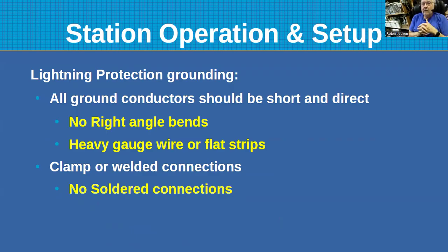Once again, you want to try to avoid right angle bends. You want to have either heavy gauge wire or flat strips. I use outside copper strap that's 2 inches wide. It has a lot of surface area, and that's where the current actually flows, on the surface. Inside, I use fairly wide braided wire, which also has a lot of surface area, and it's still flexible. And like I said, you want to make sure that you have either clamped or welded connections.